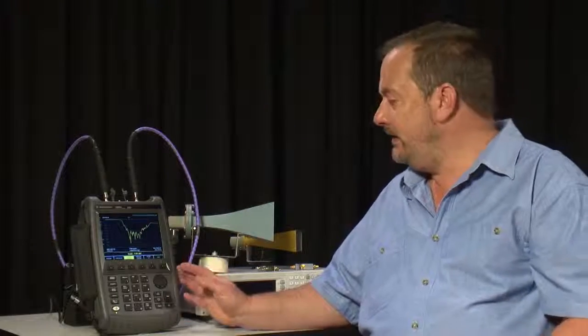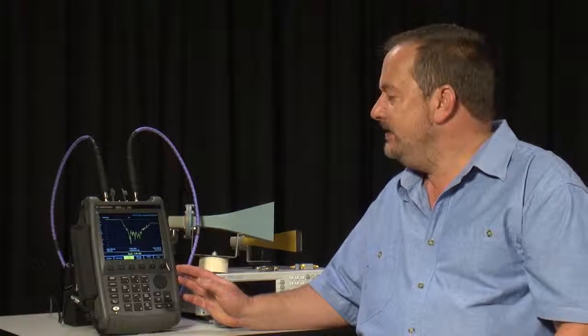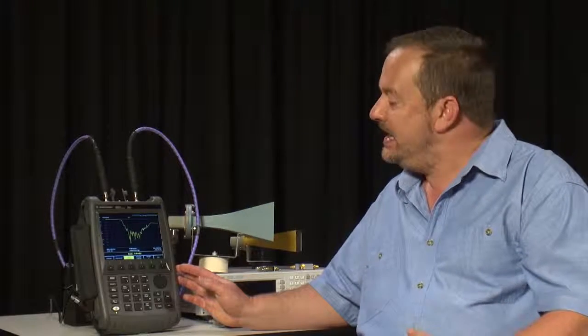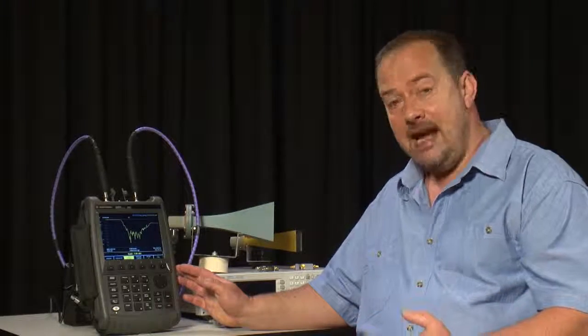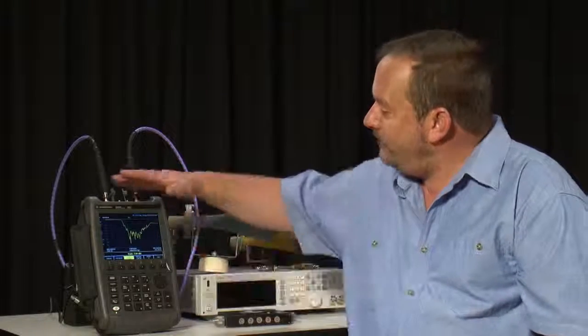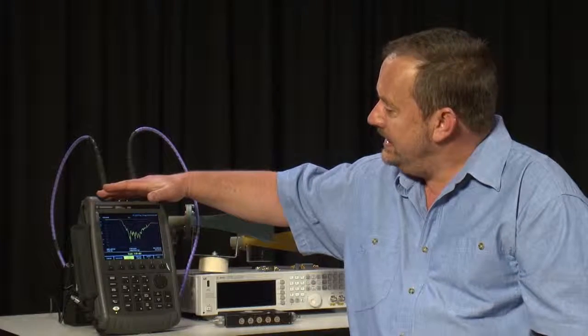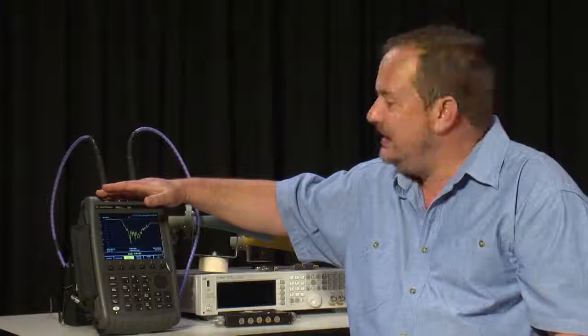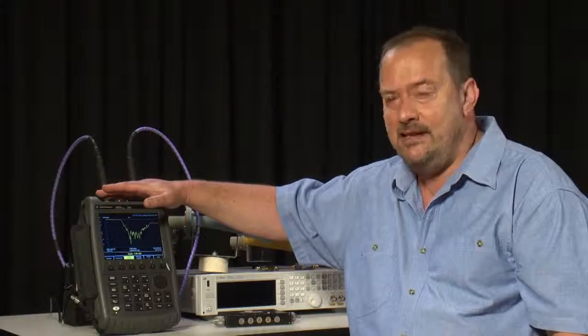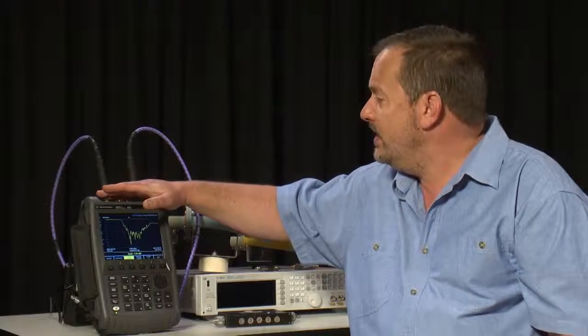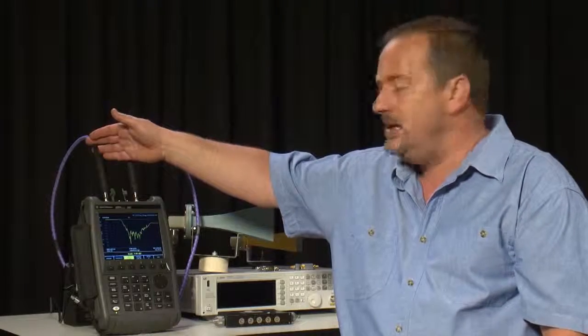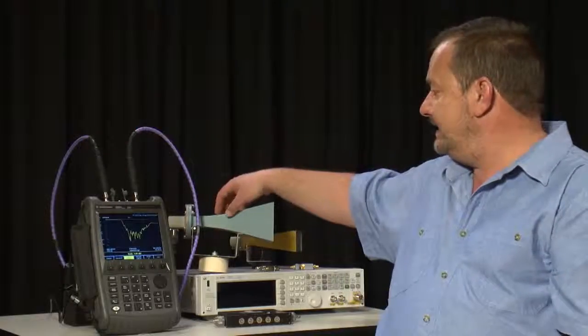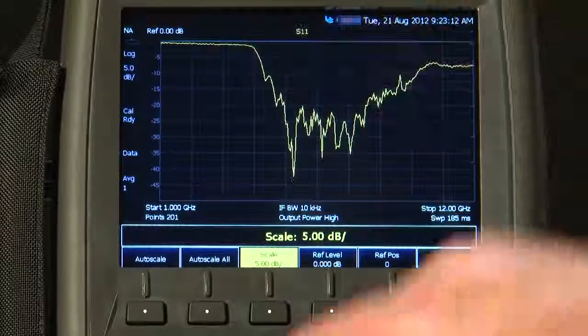Now, you will notice I have not done a calibration here, but the FieldFox has a feature called CalReady. That means that when you buy the FieldFox, it has been pre-calibrated at the Agilent factory for this point here. This reference plane on the port 1 connector has been calibrated across the entire frequency range of the FieldFox. With a short, high-quality test cable such as this, I can connect the antenna directly to the instrument.